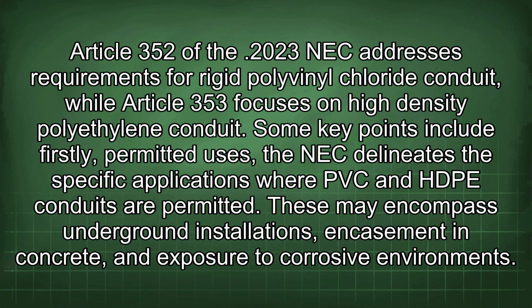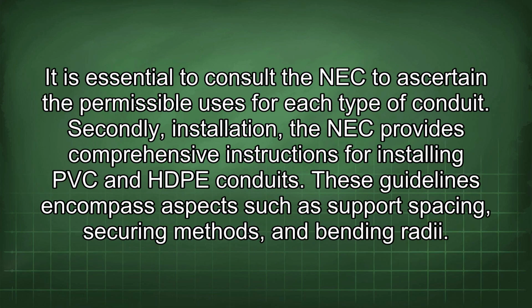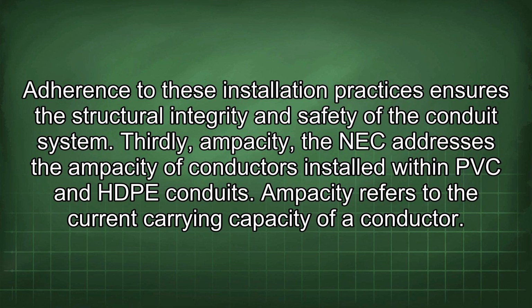These may encompass underground installations, encasement in concrete, and exposure to corrosive environments. It is essential to consult the NEC to ascertain the permissible uses for each type of conduit. Secondly, installation. The NEC provides comprehensive instructions for installing PVC and HDPE conduits. These guidelines encompass aspects such as support spacing, securing methods, and bending radii. Adherence to these installation practices ensures the structural integrity and safety of the conduit system.